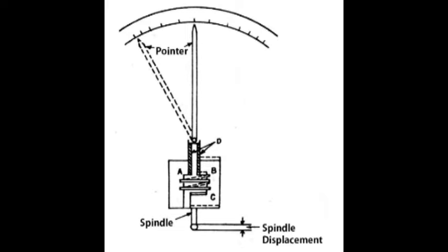It consists of a fixed block A, which is rigidly fastened to the gauge head case, and a floating block B, which carries the gauging spindle and is connected horizontally to the fixed block by the reed C. A vertical reed is attached to each block, with the upper ends joined together. These vertical reeds are indicated by D. Beyond this joint extends a pointer.